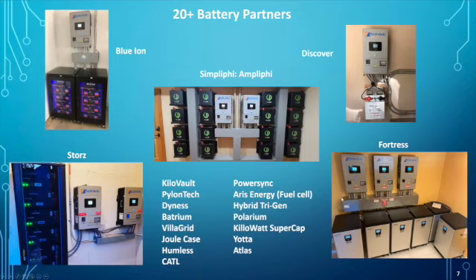This is where the battery actually programs the inverter. You don't have to program it. You just tell it the right address and enable lithium communication and the cable. And so then it aggregates the batteries up and tells it how many amp hours, what's the maximum charge and discharge rates, what voltage to charge to, what's the state of charge, what's the state of health, and so on and so forth. So it automatically adapts for different climates. It just makes it a whole lot easier, and it makes it much more accurate on the state of charge.